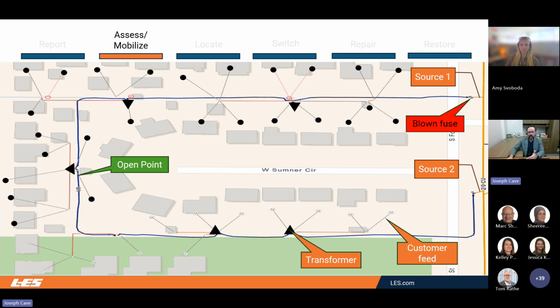So at some point, our outage management system will take that information, it'll make an assumption or make a guess to state that we think that the problem here is something upstream, so the source of the power getting into that neighborhood. So in this instance, we've got multiple transformers that have customers with outages. So it's assuming that we have a blown fuse at source number 1. So it'll populate the entire map with that assumption and show all of those customers out of service. And it'll populate all of the details for that incident with the number of customers that are connected to that source.